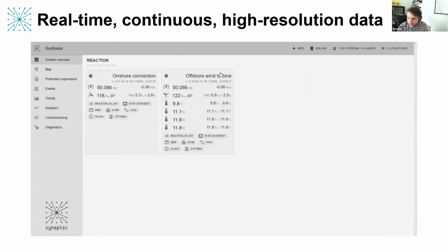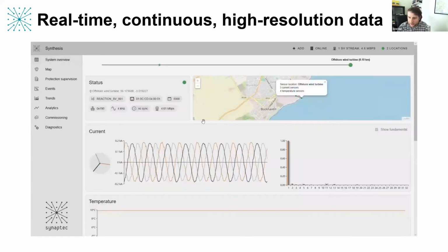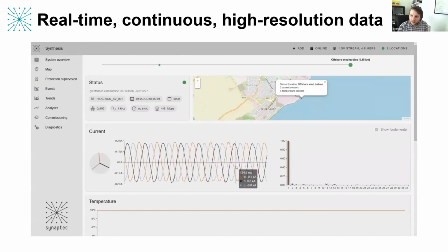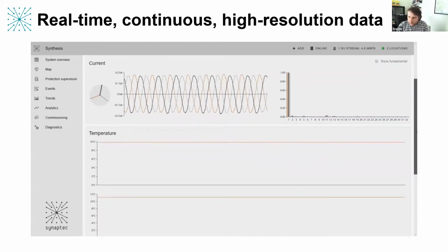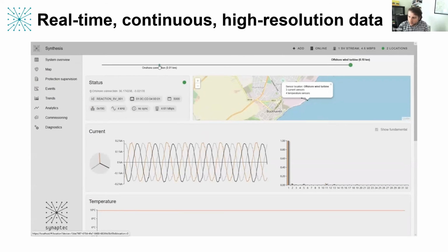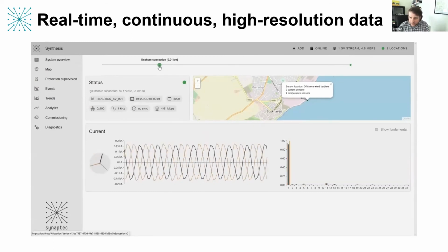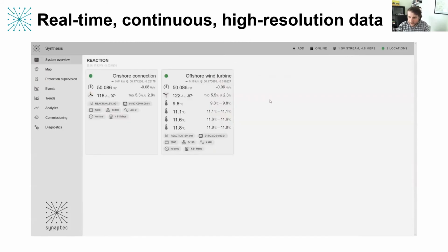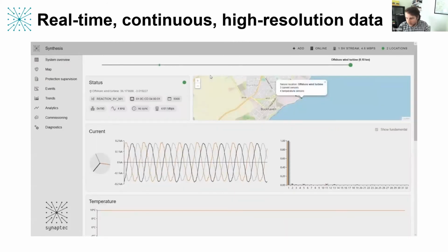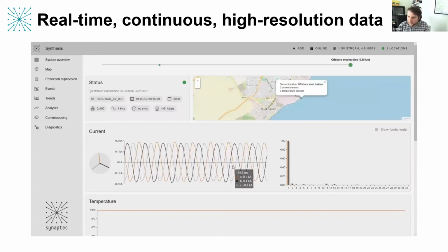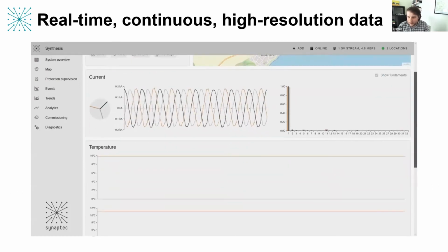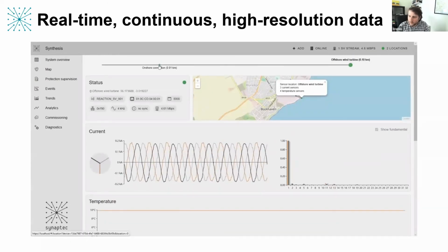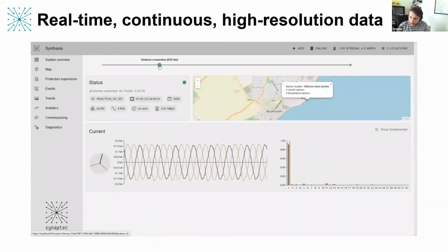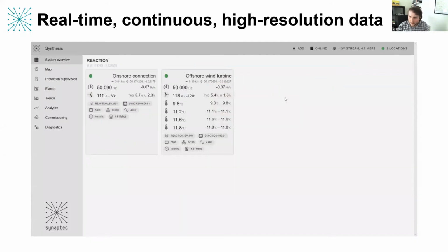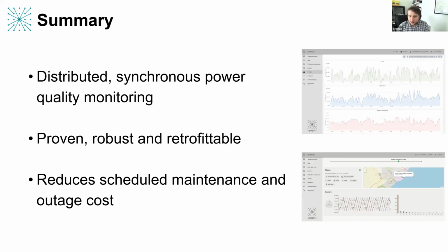So this has all been done continuously, and we're just taking a peek at that in real time as the data is being processed. This is something that's built into all of our electrical sensors, so you get the full waveform data, and you also get power quality data continuously. In this case, you can also see some of the temperature readings as well. Again, it's a fairly unexciting plot, as it's basically 10 degrees continuously, but we can also look at this data over a longer period of time to pick out trends and deviations from behavior as well. So that's really the main points that we wanted to cover.